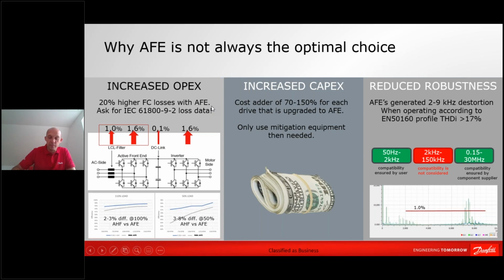And maybe here you should again be a bit cautious. There have been some standards now applying for drives, where you have to publish your losses in a given way for standard drives. Unfortunately, AFE drives have not been considered in this standard, and that means that your AFE supplier will not, as a general term, give you the loss ratio, but you should ask for them so that you can actually do your return on investment calculation for it.